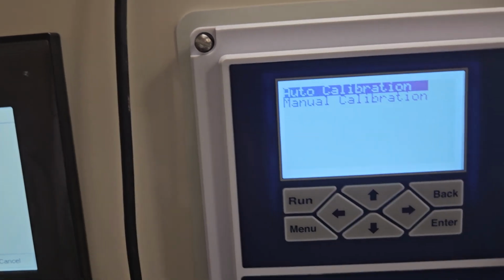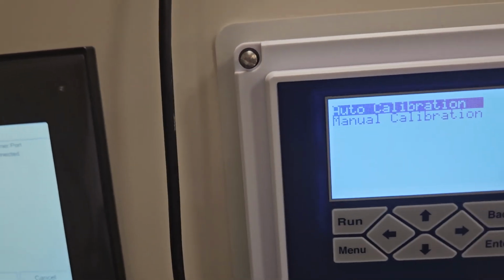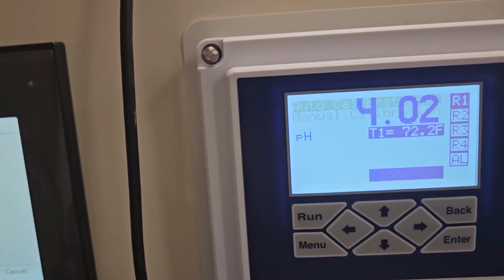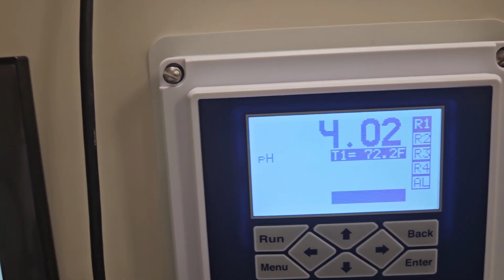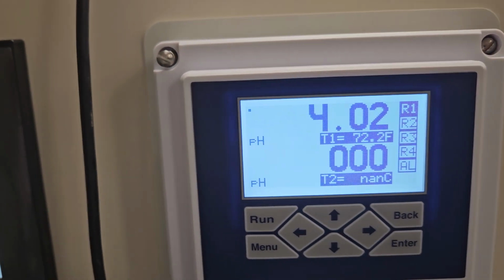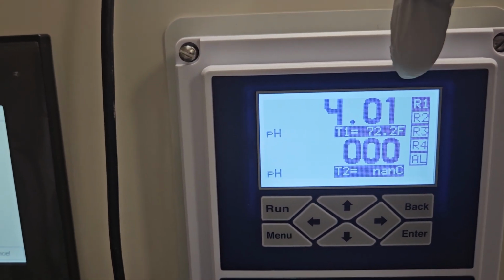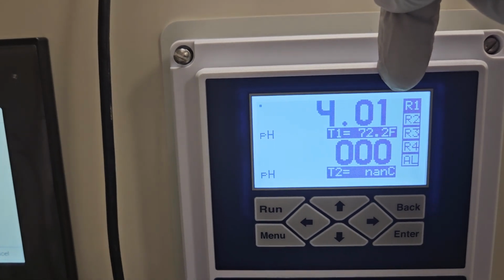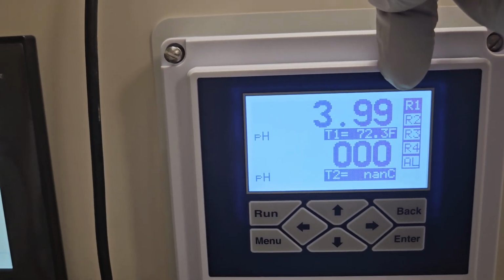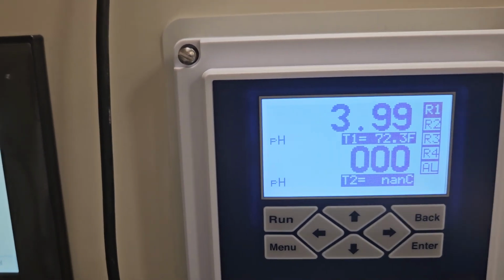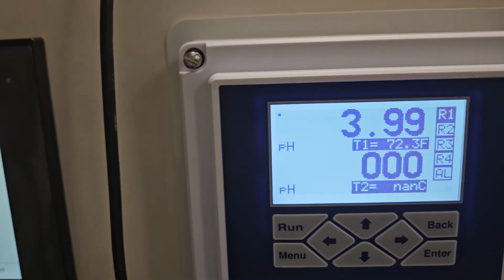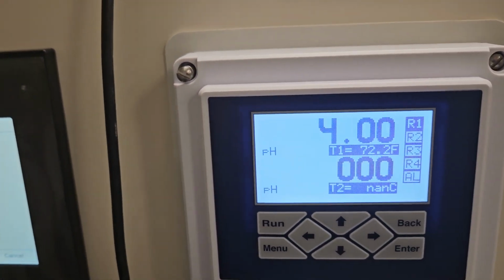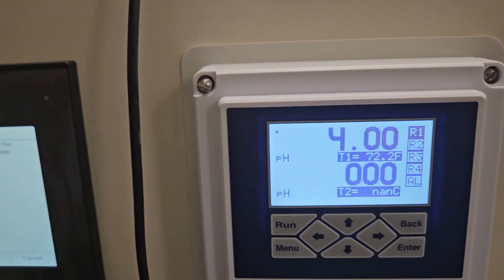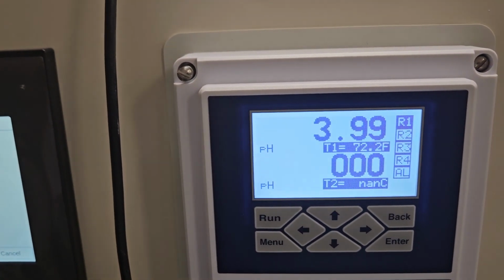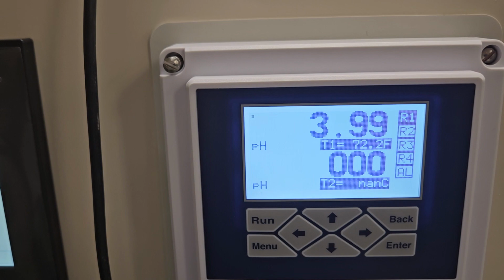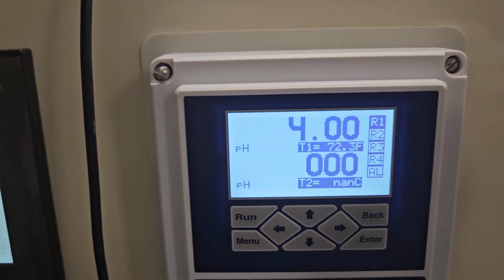That's the calibration. You can hit back to run again, and it'll put it back to the run screen, and you can now see that the pH is 4.0. I don't hold too much stock in that last digit. You really pay attention to your ones and tenths spots for the most part. You can look at the hundredths position, but it will be moving a lot, fluctuating a hundredth of a point, which is nothing really.